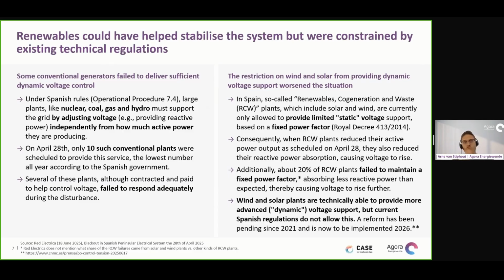On the other side, we have renewables, and they fall under another kind of regulation in Spain at the moment, which means this regulation stipulates they have to provide the more limited static voltage support. So this is to say a fixed power factor or a fixed ratio of active and reactive power. Reactive power is the part we use to manage voltage. And what seems to us have happened is when they first decreased their dispatch, as they were scheduled to, this meant less reactive power absorption, which meant increasing voltages as a consequence thereof.